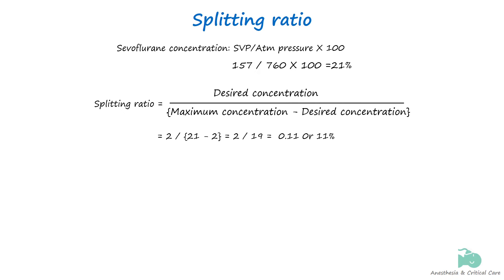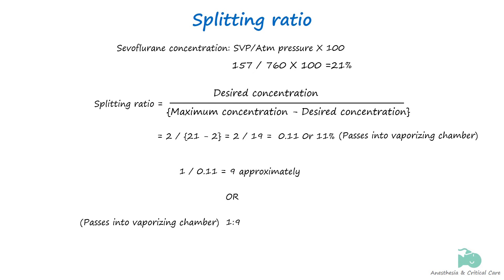We can also convert this value into a ratio by dividing 1 by 0.11, which equals approximately 9. This means for every one part of fresh gas that passes through the vaporizing chamber, approximately 9 parts of fresh gas bypass it. Note that this calculation is a simplified way of looking at the splitting ratio, as there are many factors that impact the ratio.